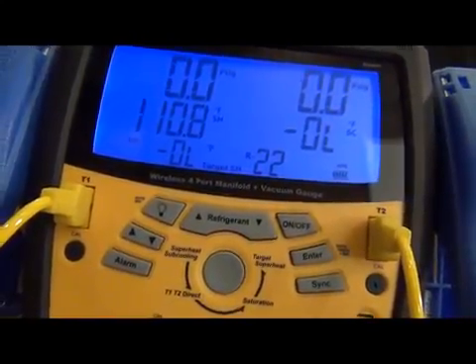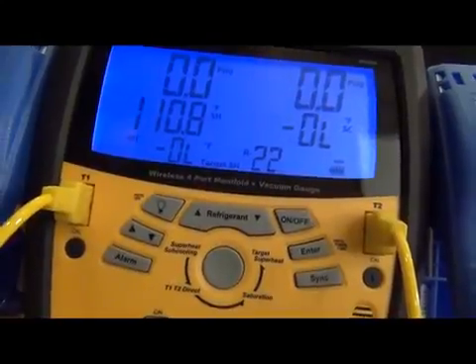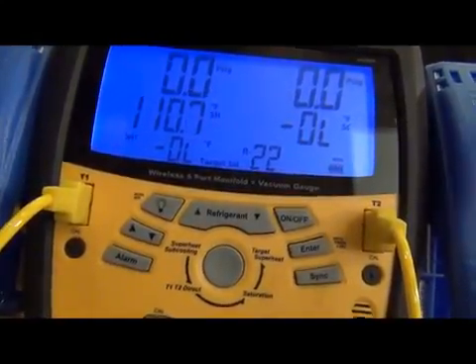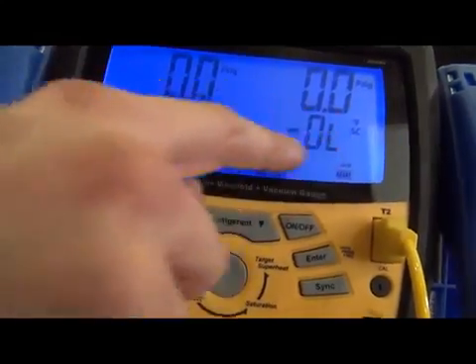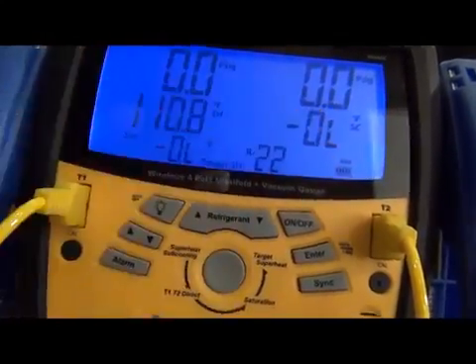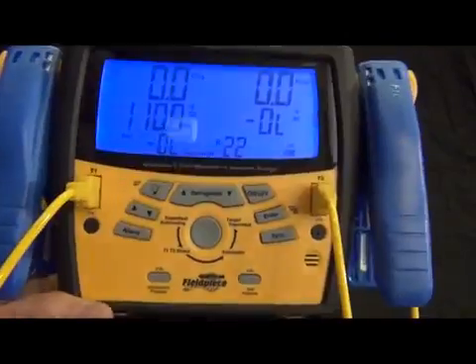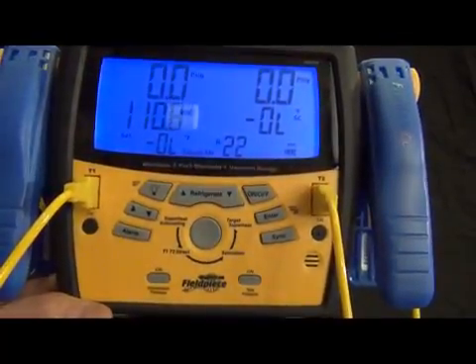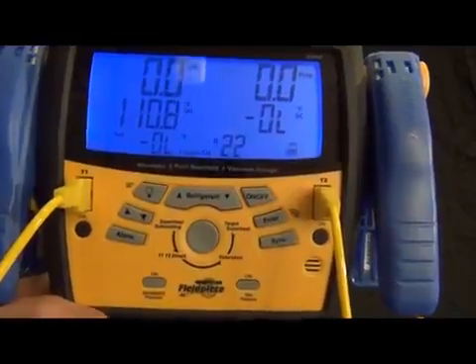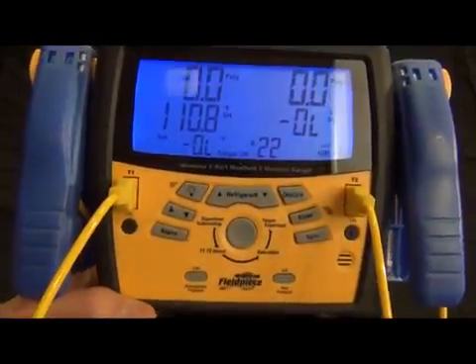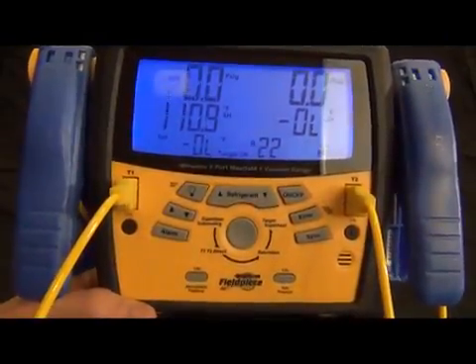And then as you turn off the pump and shut down the system, the microns start creeping up again and it'll go off once it hits 1,000. There also will be a timer in this display right here that you can actually see how long it took. A lot of manufacturers will spec out that it needs to stay under, for example, 1,000 microns for three or four minutes or whatever they spec out. And this way you can measure all of that.